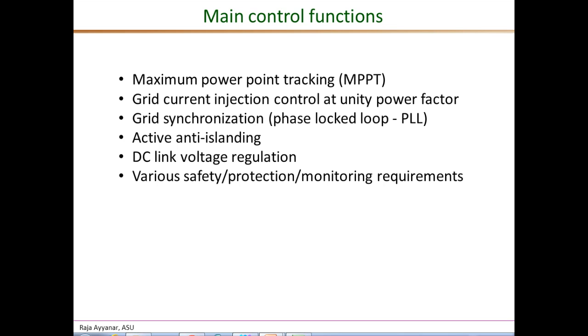The main control functions or the main control loops present in all string inverters are listed here. As we saw in the previous slide, the MPPT is a major control requirement, and this is done by a dedicated control loop using one of many different MPPT algorithms. Then we need to have an AC current control loop, which injects the current at unity power factor at present.